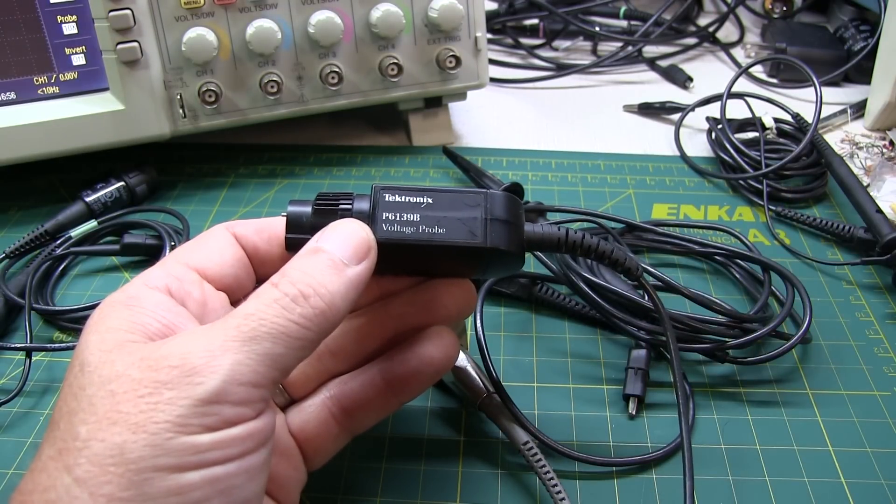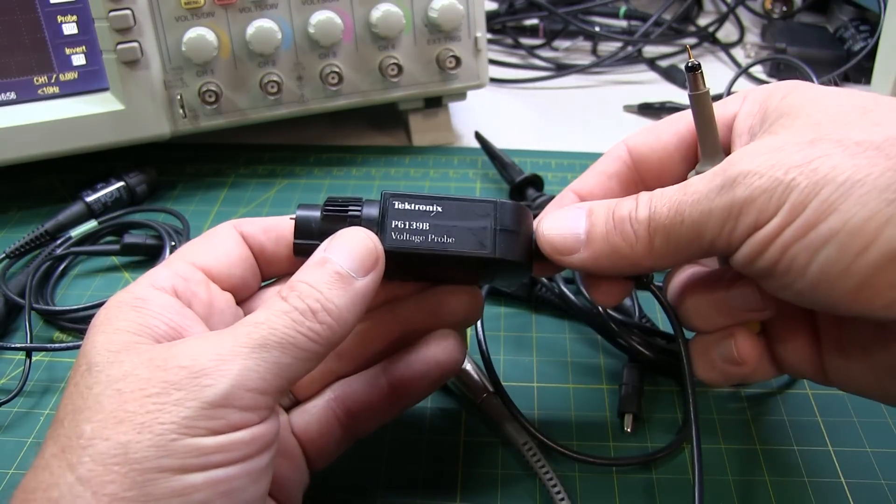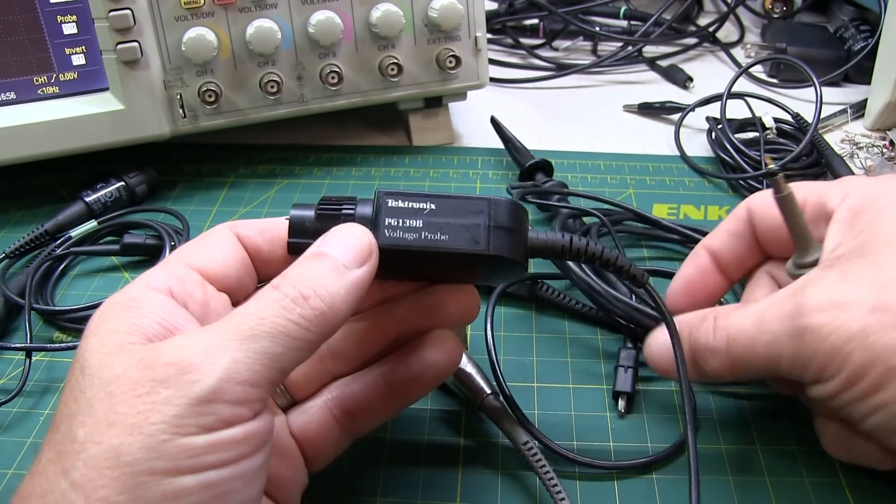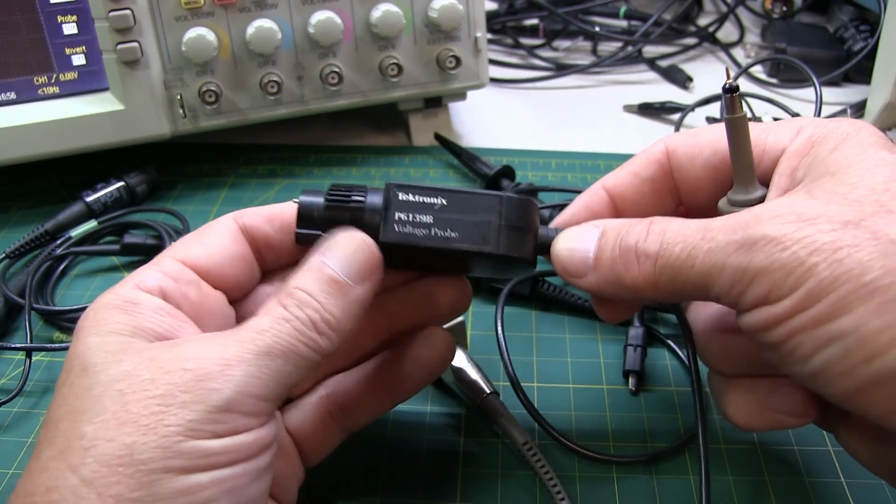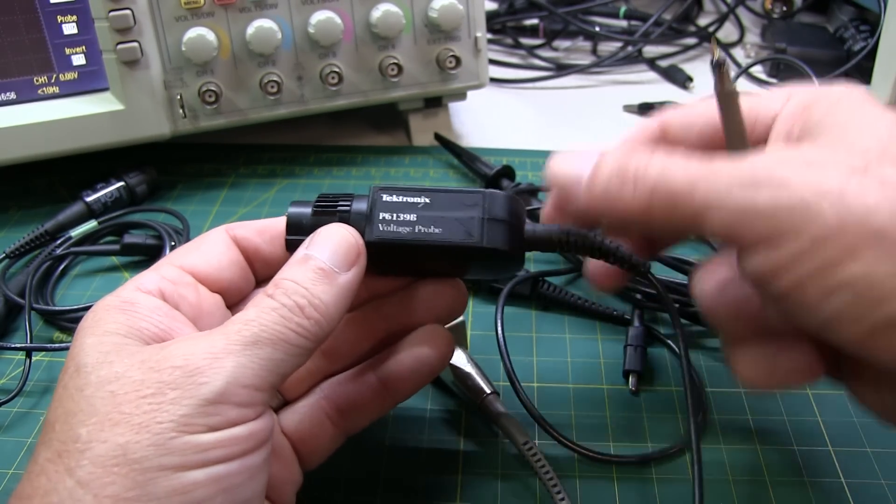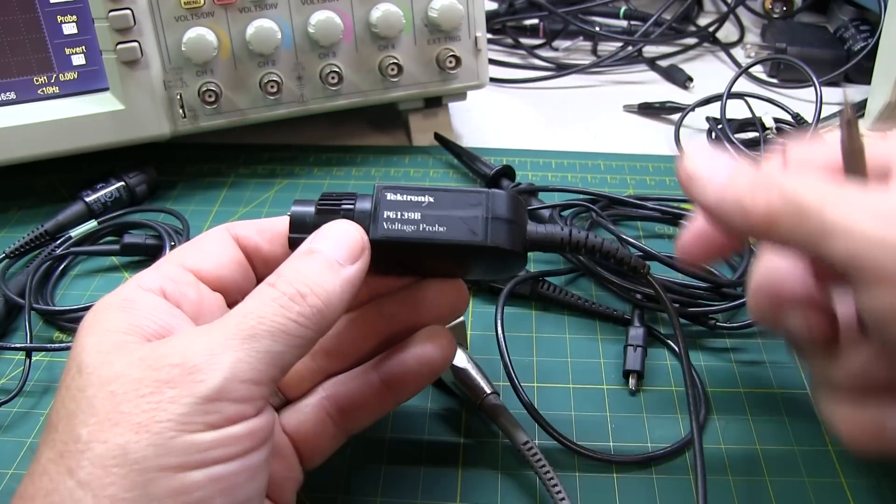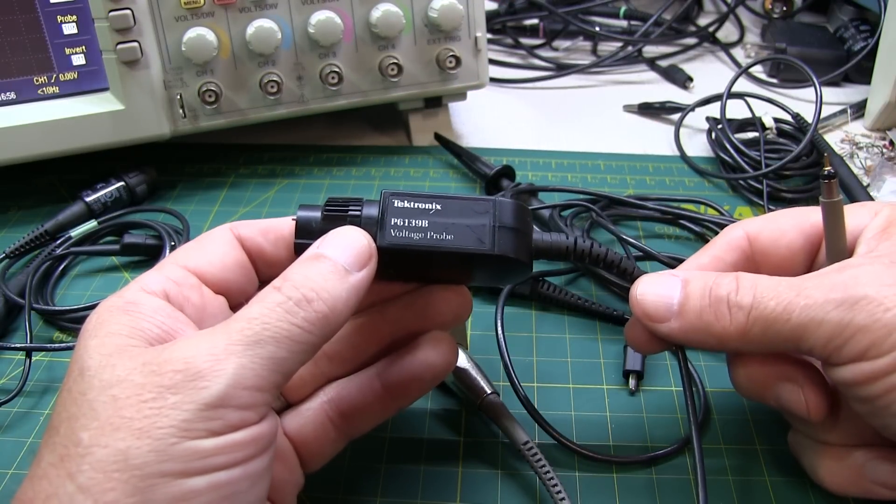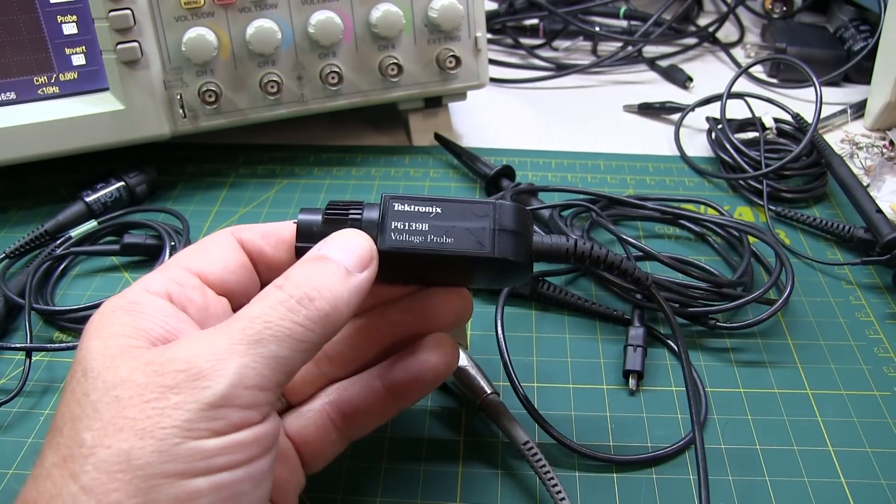So in general, if you're not matching a Tektronix probe to a Tektronix scope, it's probably okay to select a probe whose bandwidth is a little bit greater than the oscilloscope bandwidth that you're using so that you can achieve the full rated scope bandwidth when used in combination.